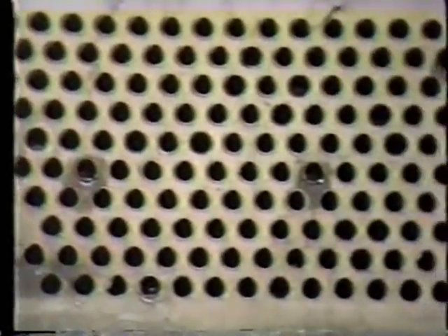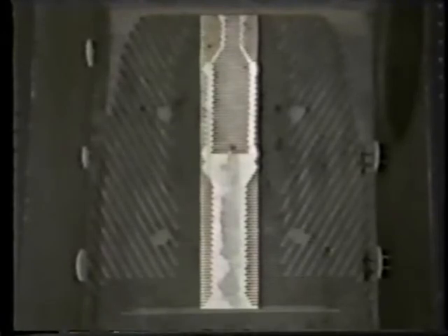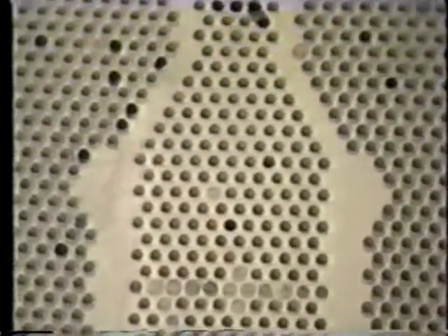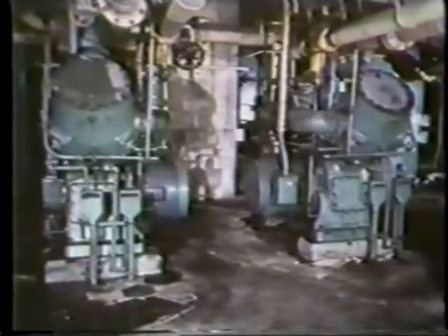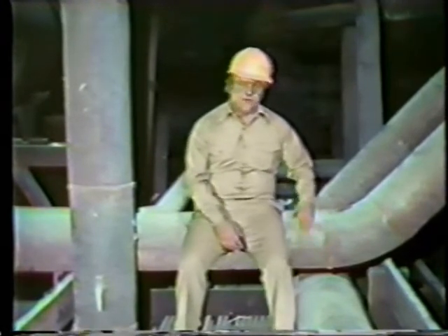During the condensing process, air and non-condensable gases are released from the condensate. This air continues to flow with the steam. As we noted earlier, the air exit lane is the lowest pressure area in the condenser. The steam-air mixture will flow into the air exit lane and up through the tubes in the air cooler section. The cool water in these tubes will cause nearly all the steam to condense, leaving only air at the top of the air exit lane. This minimizes steam and moisture carryover into the air removal system. The air at the top of the air exit lane collects in this pipe and is removed through the air offtake pipe.